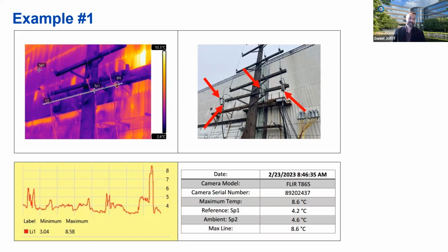What this implies to us is that you've got a very inefficient connection. You've got a dirty connection. And instead of efficient energy transfer, we've got energy going into heating up these components. And it goes without being said, once they heat up to a certain degree, they're going to begin to fail. And when they fail, we get plant shutdowns and business interruption.